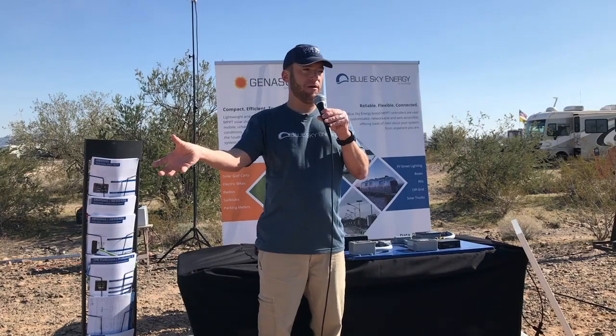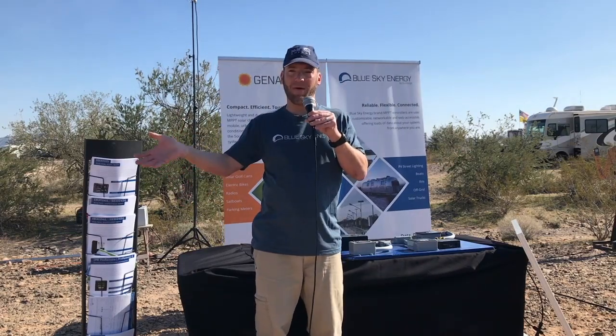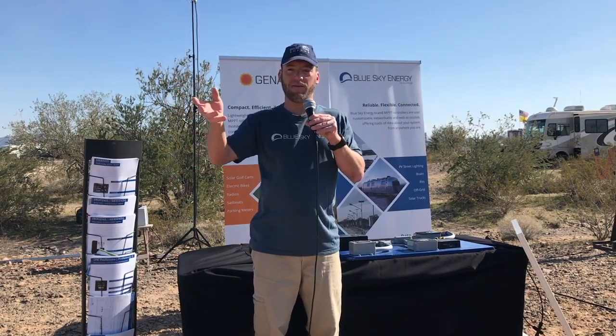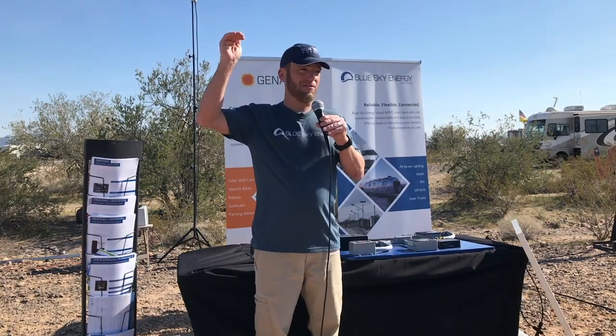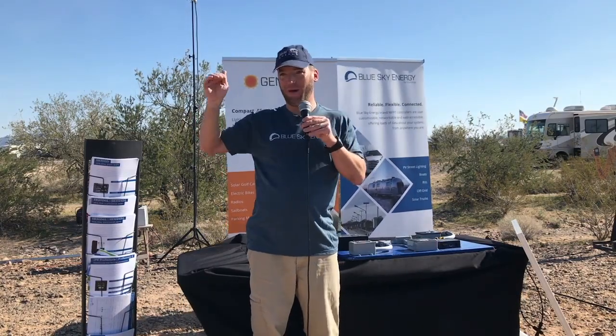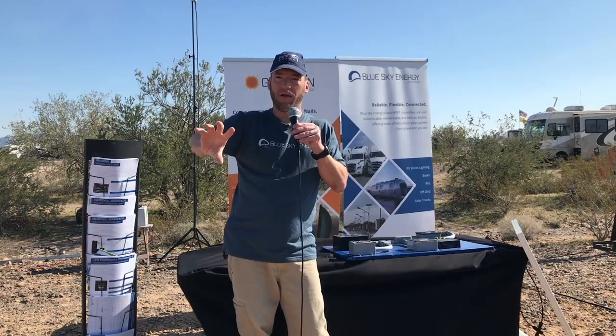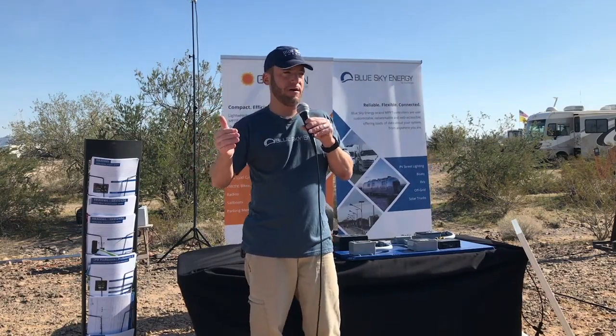Now if you put a load on the system, let's call it a 5 amp load, that load's going to try to make the voltage fall. So the controller says, voltage is falling, I'm going to turn up my output. Now it's putting out 10 amps, 5 to the battery, 5 to the loads. Then you take away that load, the voltage tries to increase because the battery only needs 5 amps, so it turns down its output. It's providing enough current to maintain a voltage.